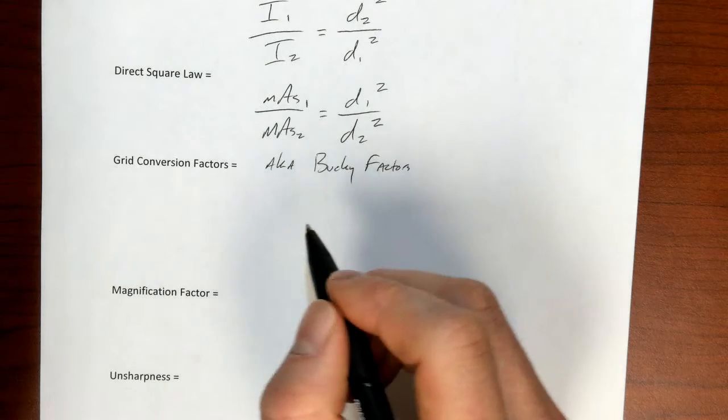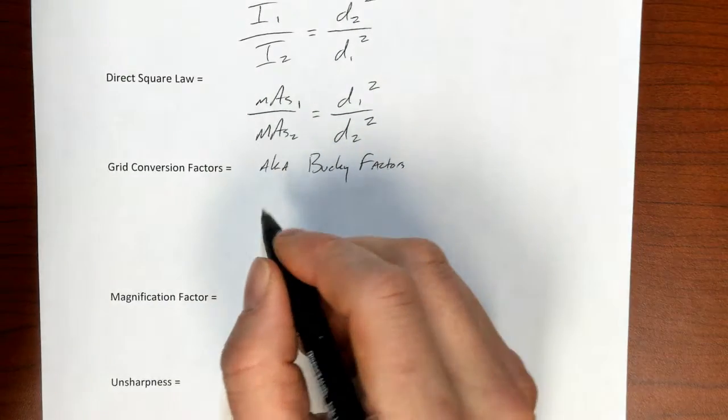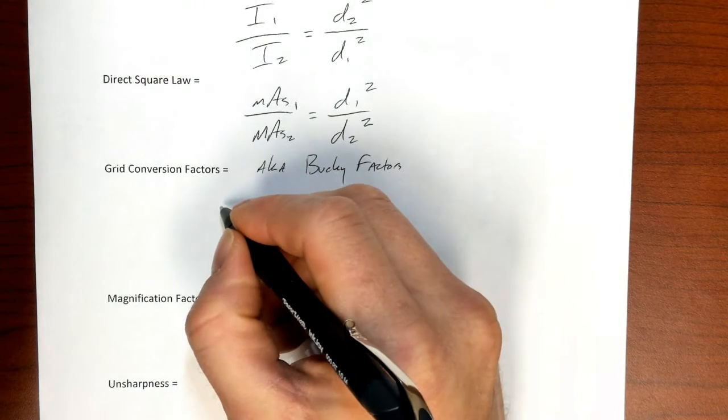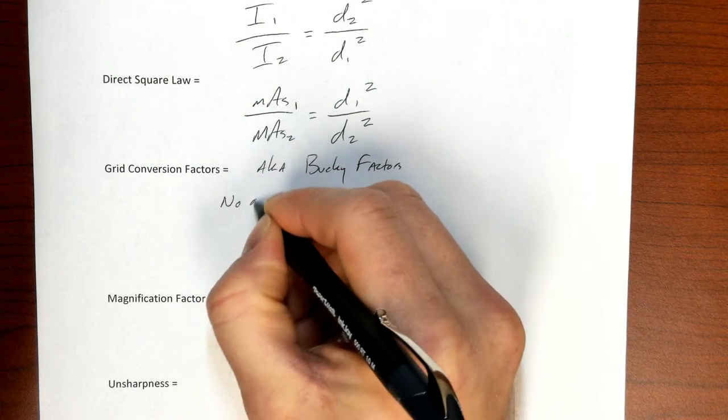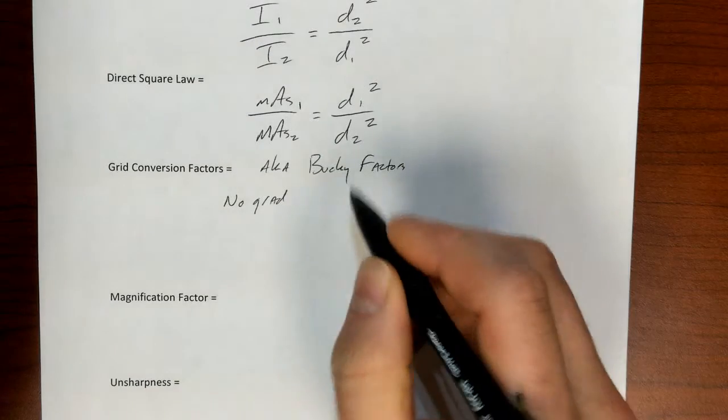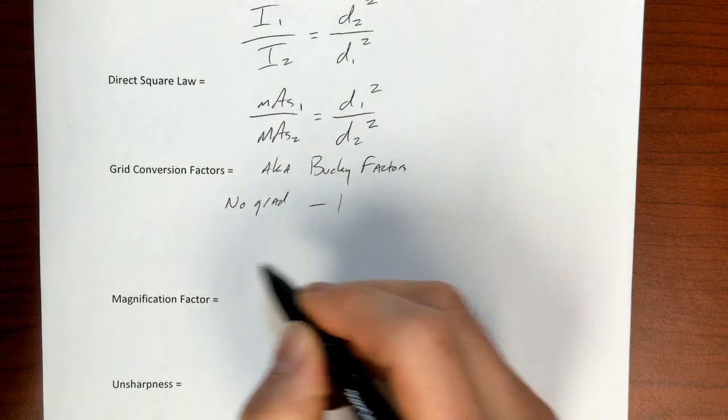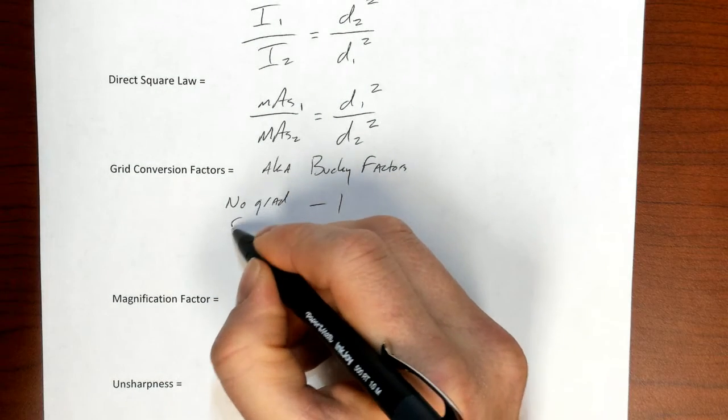Grids are used to clean up contrast and get rid of scatter radiation. In all likelihood, they will go away in the next 5, 10 years, and we will use software algorithms to correct for scatter on the image. But for right now, we're using grids to clean up. And if we're not using a grid, then we'll have a Bucky factor of 1.